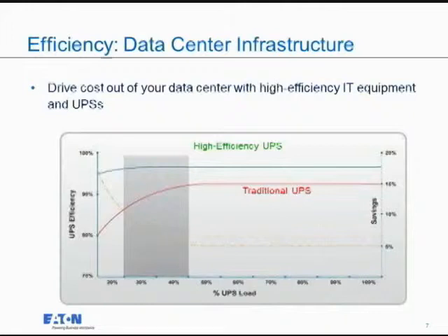We're increasing the efficiency. So we increase the efficiency from a 93, 92% up to 94, 95%, but at the same time, we maintain it for longer. So when we get into the sweet spot or the typical operating range, we see savings increase from 5% to 10% to 15% at extremely low loads.